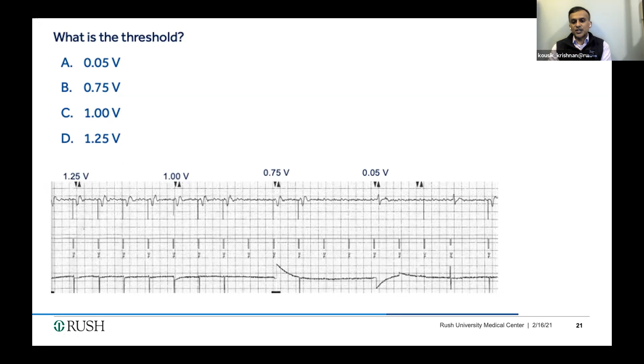So now let's move on to another important concept, and that is, we can pace all the time, and that's great, and we can figure out outputs, but some patients don't need pacing every single beat of their life. And we need the device to know when it's appropriate to pace and when it's not appropriate to pace. And that's the concept of sensing. Sensing is the ability of the pacemaker to see when the patient has an intrinsic or natural depolarization occurring. And they need to sense that signal.